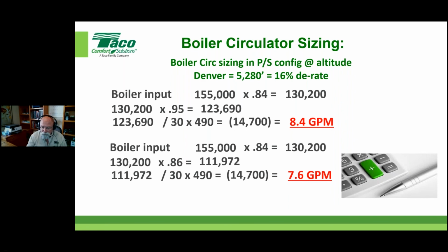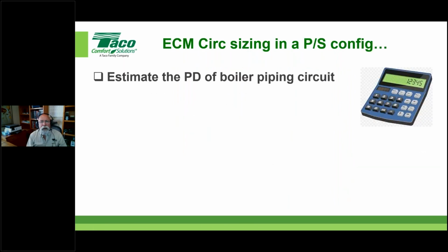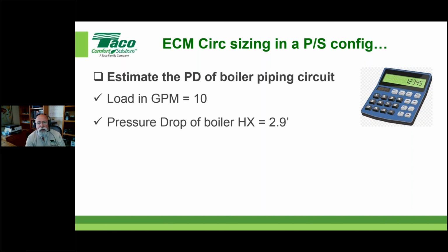Hopefully my point's made. So anyway, in order to do this right, again, these are generalizations, not having the boiler's manual available at midnight, New Year's Eve, etc. We have to estimate what the pressure drop of the boiler piping circuit is at that given load. I'm showing you the load being 10 gallons a minute, right? Well, the pressure drop of the boiler heat exchanger, if it's a water tube style heat exchanger, might be 3 or 4 times this number.